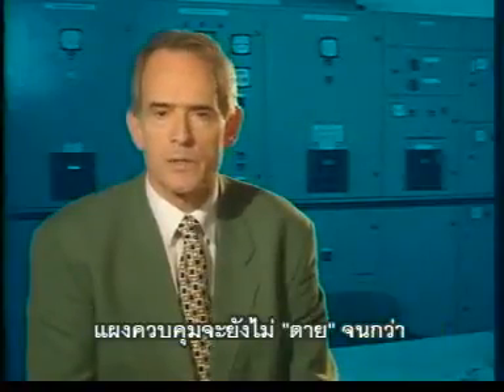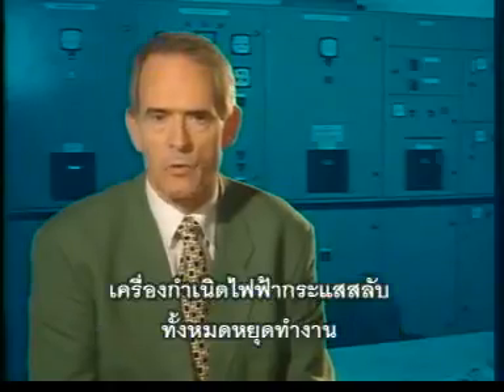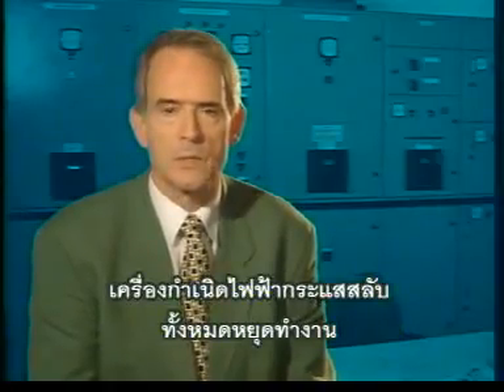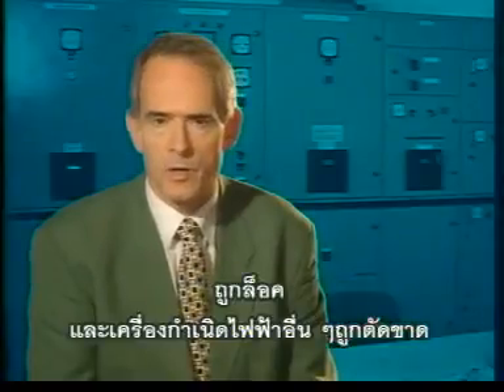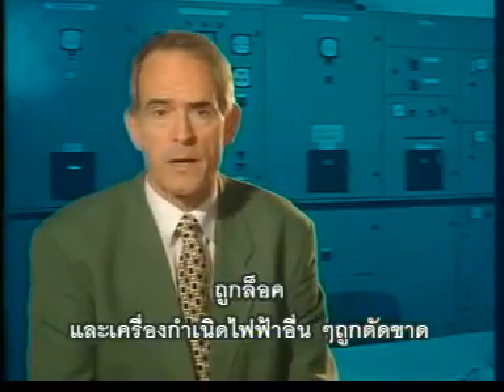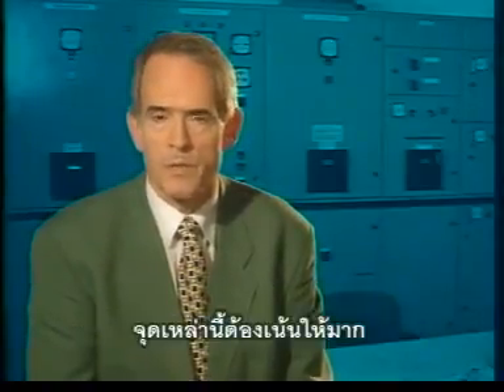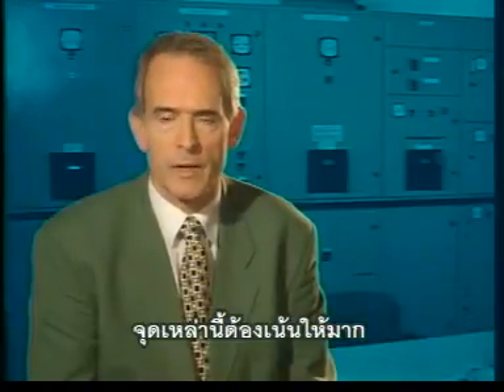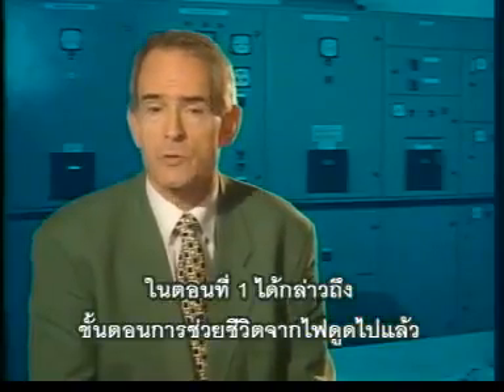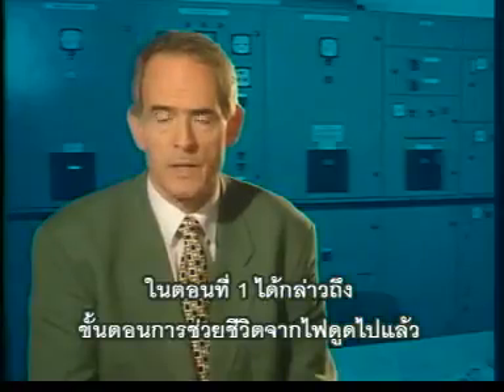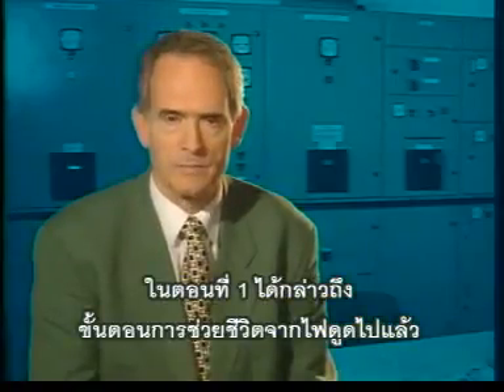A switchboard can never be considered dead unless all AC generators connected to it are stopped, locked off, and all other supplies are disconnected. These points can never be emphasized strongly enough. The electrical rescue procedure is described in Programme 1 of this series.